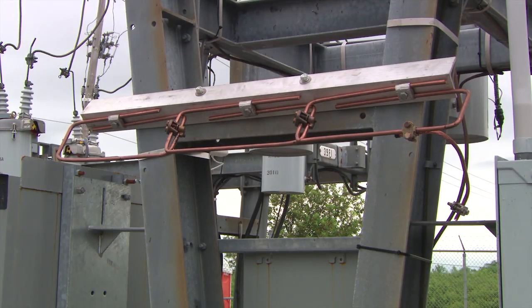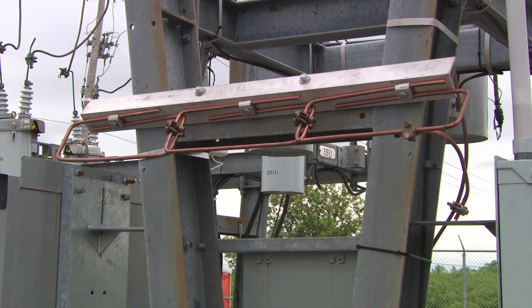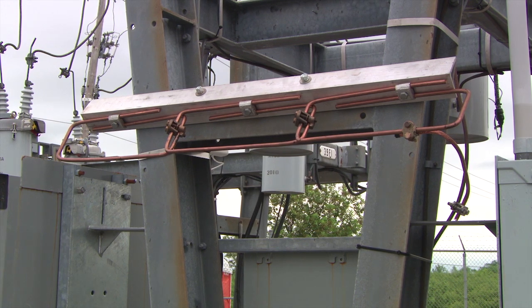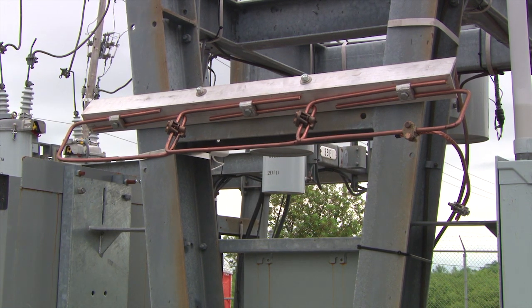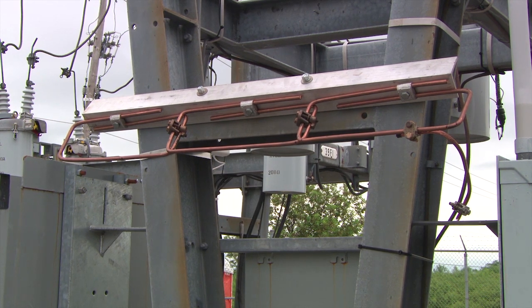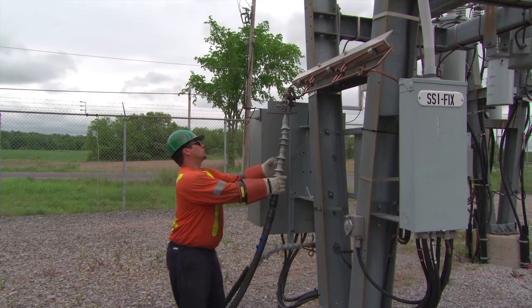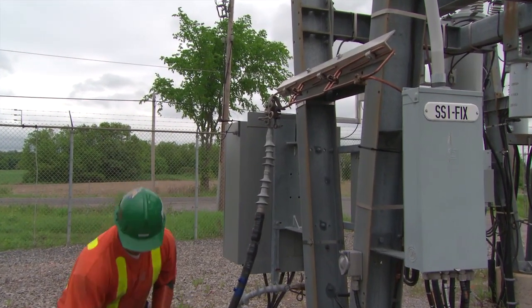Prior to laying out the low-voltage cables, ensure that adequate grounding facilities are available in order to conveniently hang and ground all cables. Many crews make up temporary or portable units and ground them to the station ground prior to hanging cables. This is an example of a temporary grounding system used for low-voltage cables. When installed, it should be located in a convenient location to hang the live line end of the feeder cables.